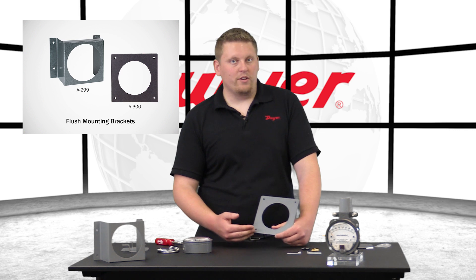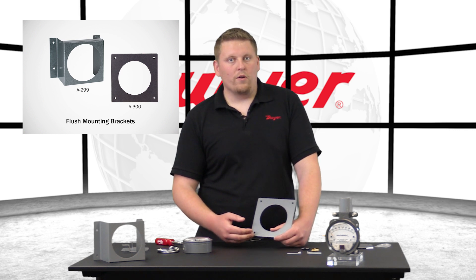When flush mounting your standard Magnehelic Gauge, you'll need to begin with a 4 and 9/16th inch diameter opening in the panel. Flush mounting can be accomplished by using our A-300 flat aluminum bracket or A-299 aluminum mounting bracket.